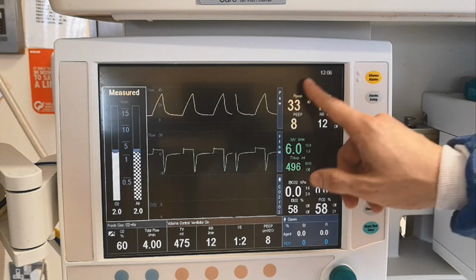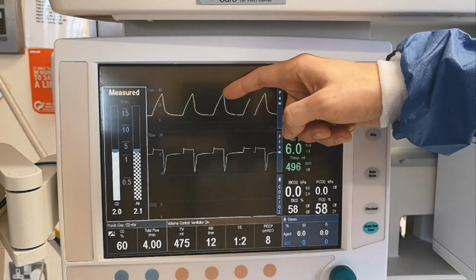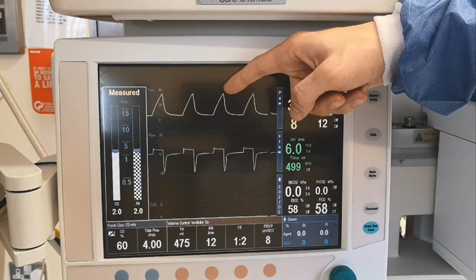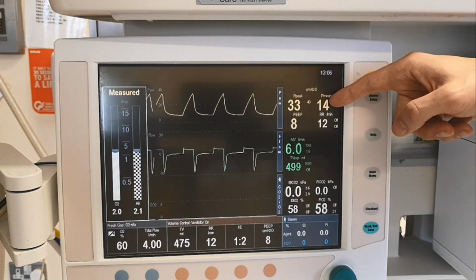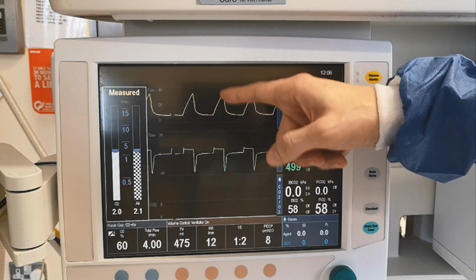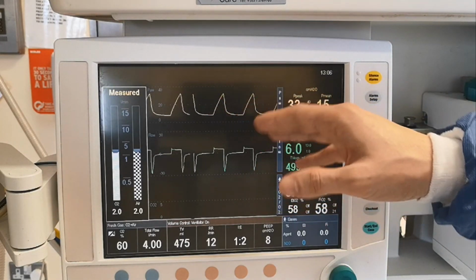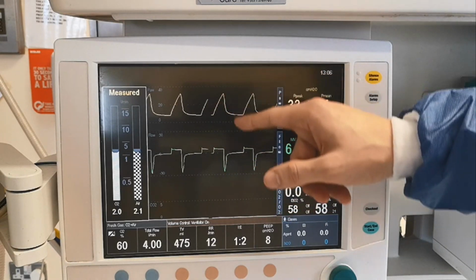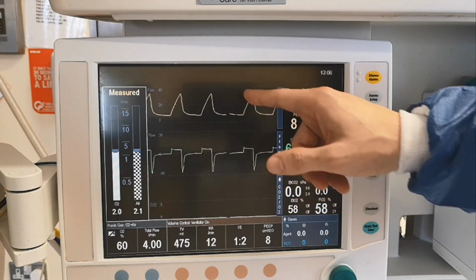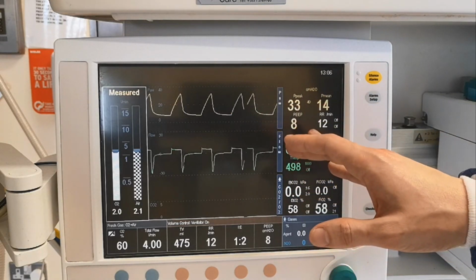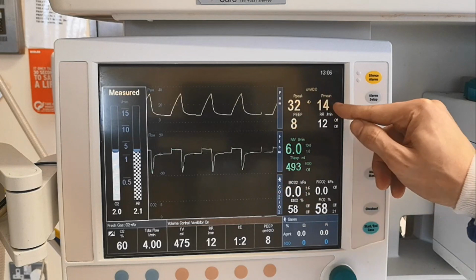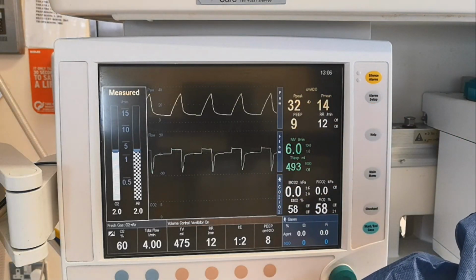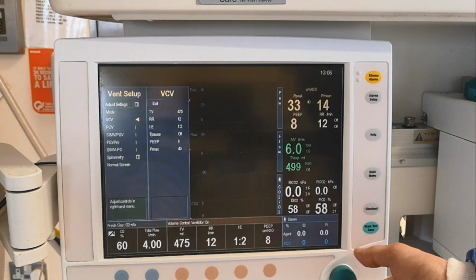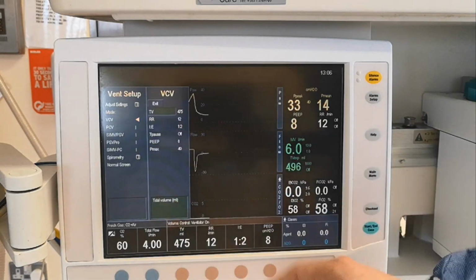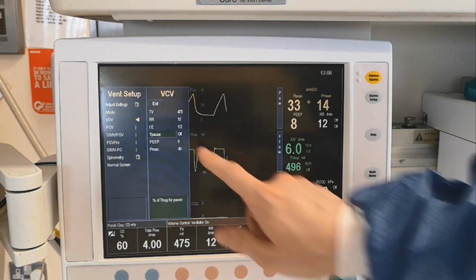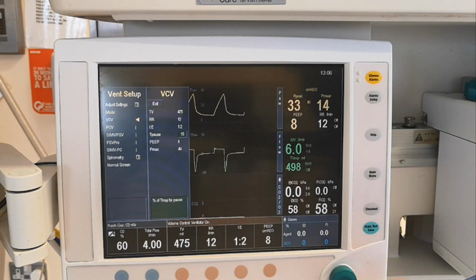Anyway, coming back to these numbers, you have the peak pressure. So that's the peak here. The mean pressure is the mean pressure generated in the airways. Now here it is not really reading the mean pressure; it's just making an average of the peak and the minimum pressure. If you want to read the real mean pressure, you want to go into ventilator setup. You want to go into the volume modes, settings, and you want to change the settings. You put a little pause here, okay? A pause of, let's say, 20.